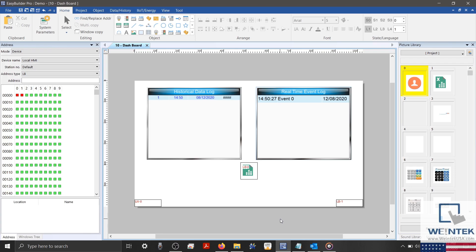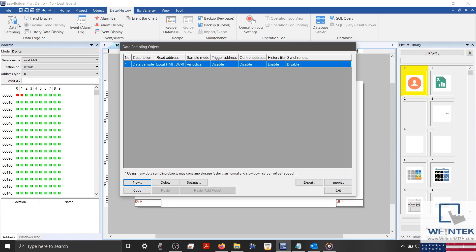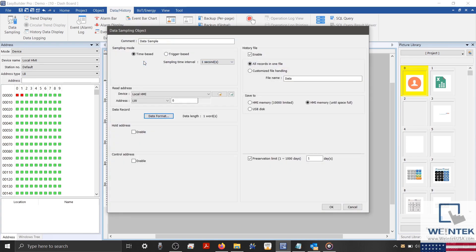Let's take a look at the configuration of our data sampling object. I'll select the Data/History tab, and on the left, I'll select Data Sampling. In this menu, I'll click my Data Sampling object and explain my current configuration. Within this project, I'm logging one word of numeric data from local word zero at an interval of once per second. I have not configured a hold or control address, but I have enabled history files, as this must be enabled prior to creating the object that will generate CSV files within your project.